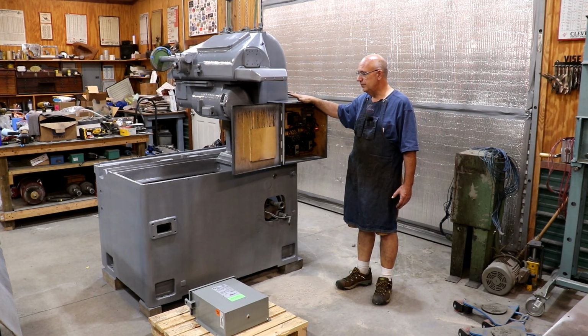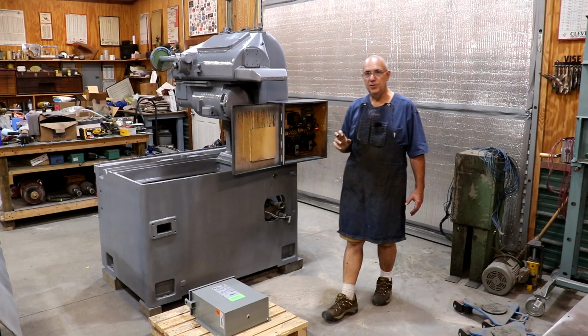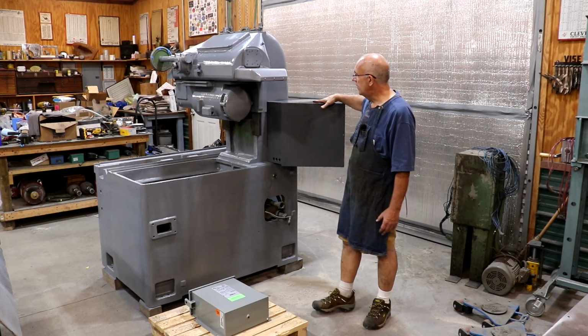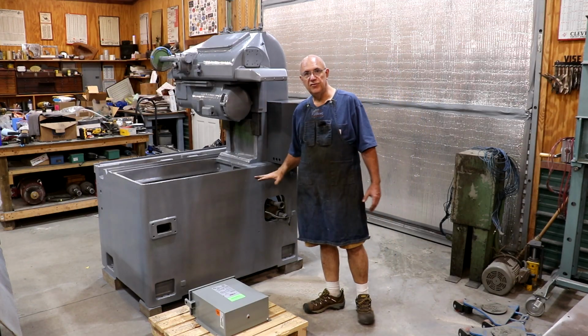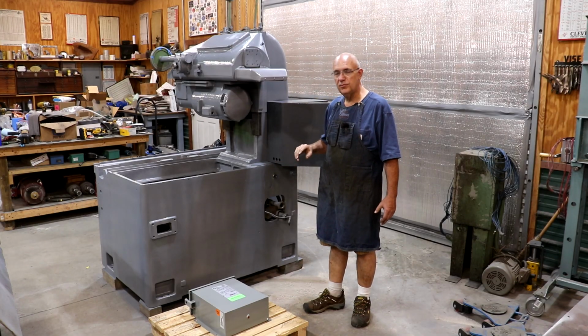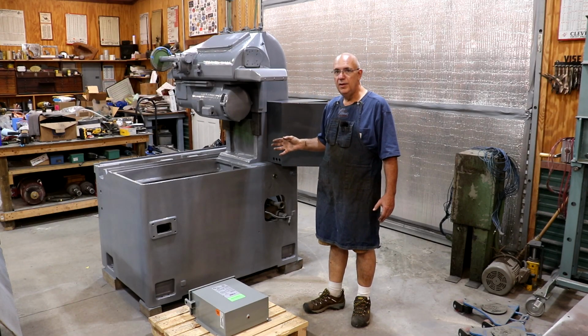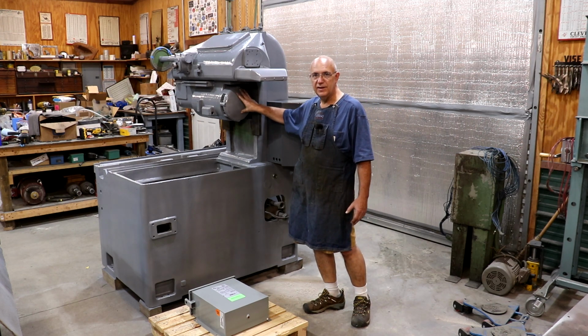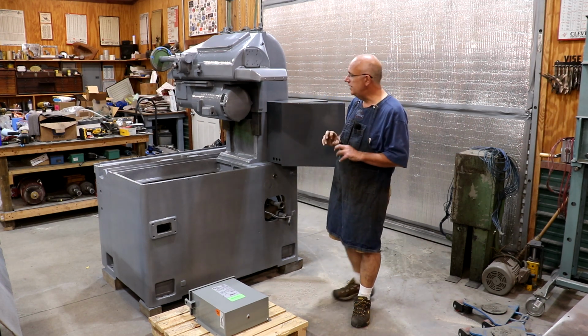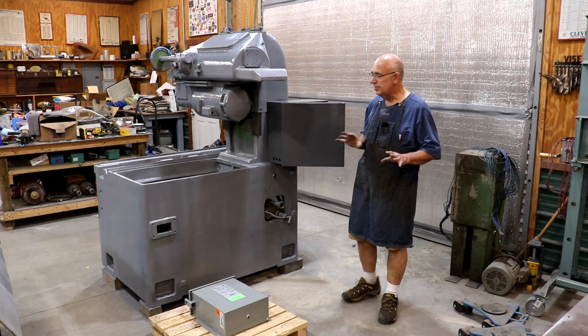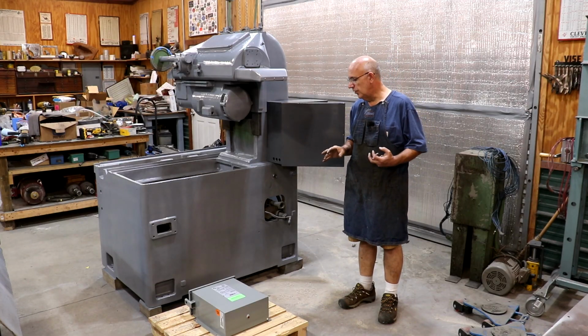One option when that kind of situation comes up is you can come in and change the wiring on your motors to convert from 440 volts to 220 volts. Most motors have 9 leads coming out of them, and depending how those leads are tied together, you can set it up for either high voltage or low voltage.